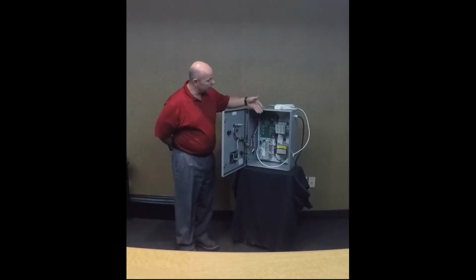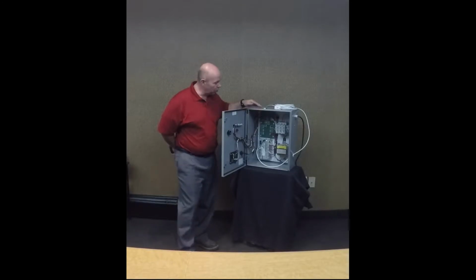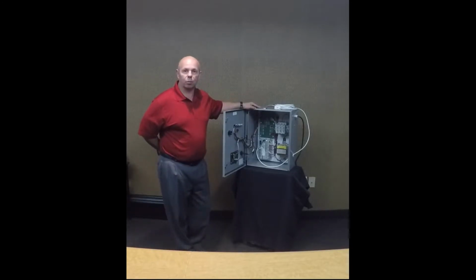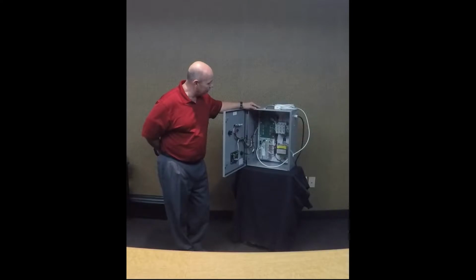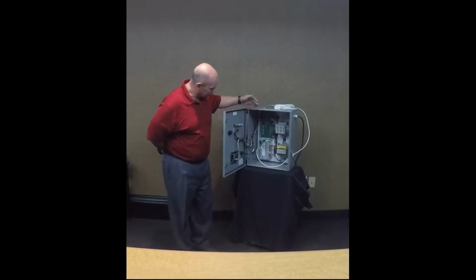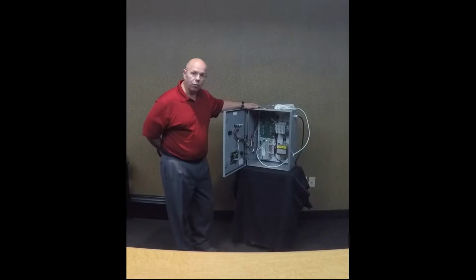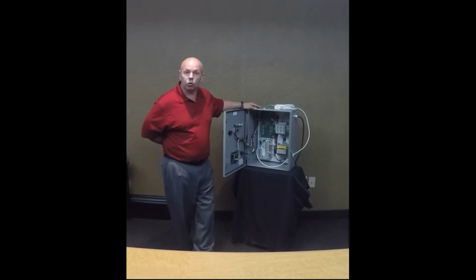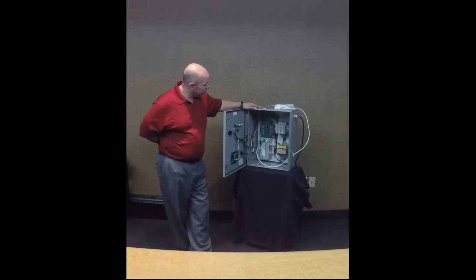The voltage comes into the transformer, step down to the appropriate voltage. On the secondary side of the transformer, we have 120 and 24 volts available. That power is fed to the relay as well as to the customer interface board. The customer interface board then would go out to the shunt trip mechanism for the circuit breaker that would be immediately upstream of your switchgear, switchboard, motor control panel, industrial control panel, or machine.